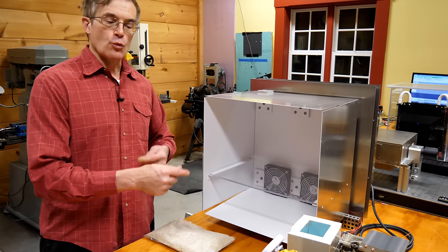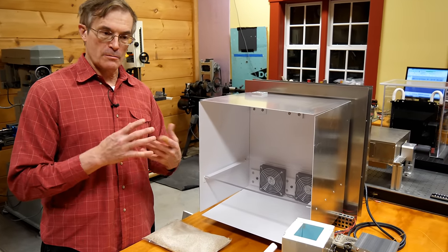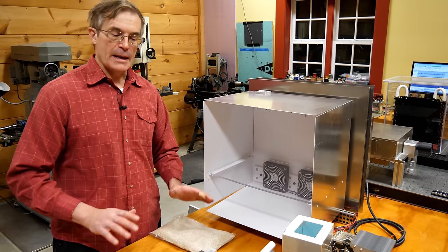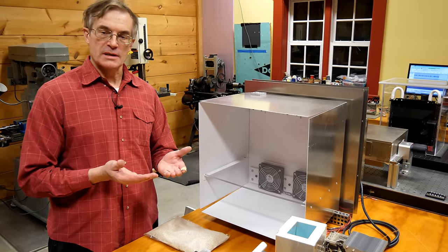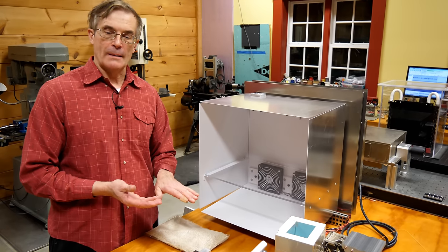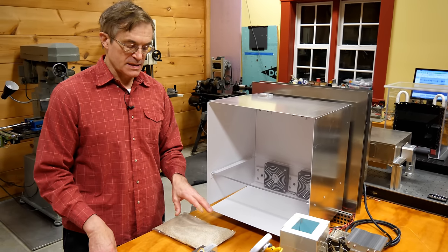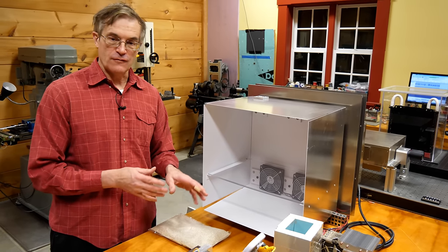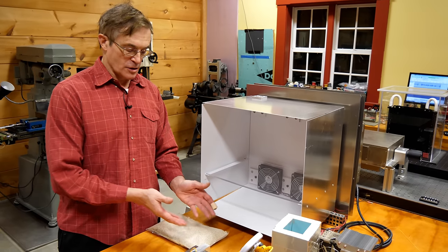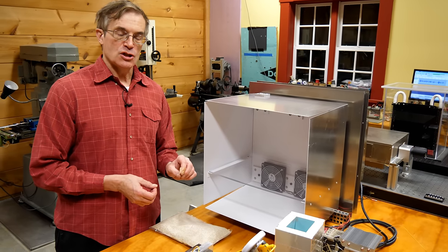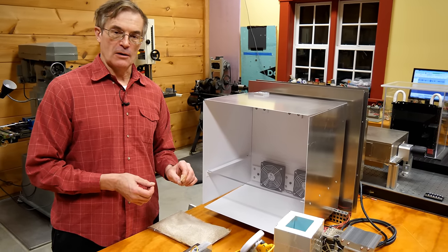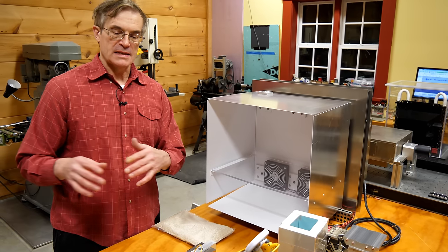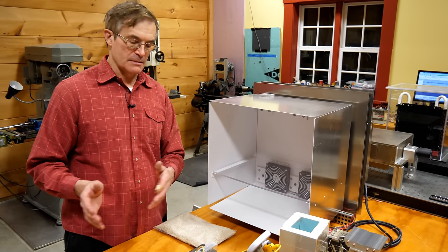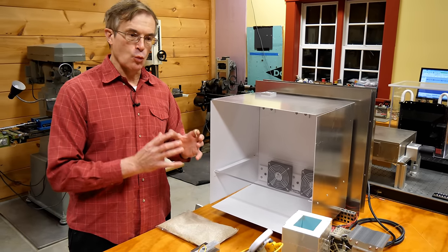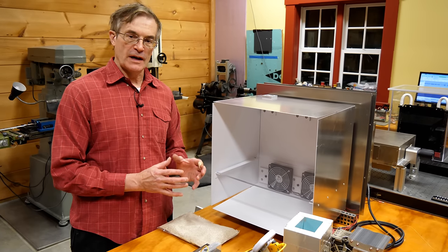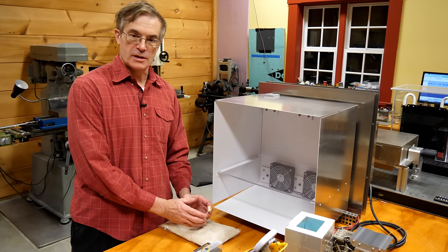Consequently, you can then reintroduce humidity either through a mist or a moist surface and bring the humidity back up to where it started, but the temperature has now dropped. One of the neat things about this process is obviously it doesn't involve any kind of fluorocarbons, just water and an inert desiccant. And in addition, it doesn't require very much electrical power, because all you need electricity for in this case is to power the low-speed fans that move the air. The work for the refrigeration is provided either by combustion or even concentrated solar.